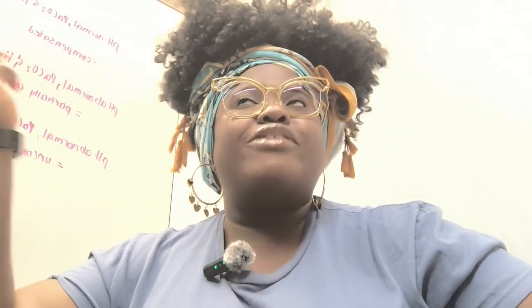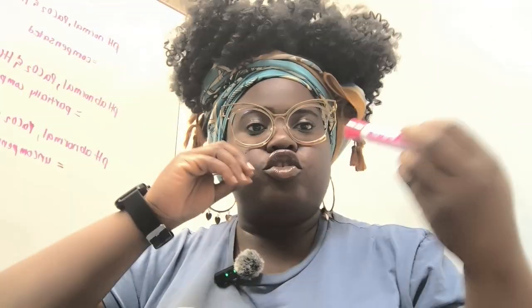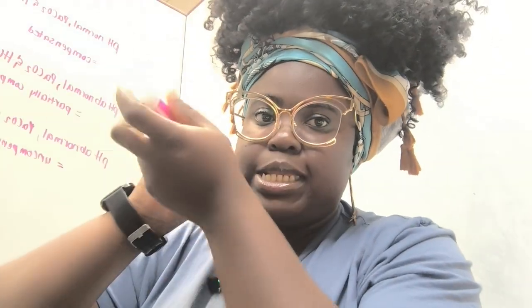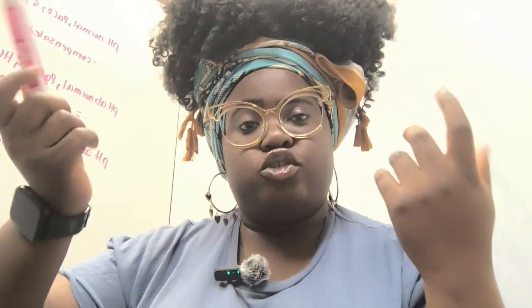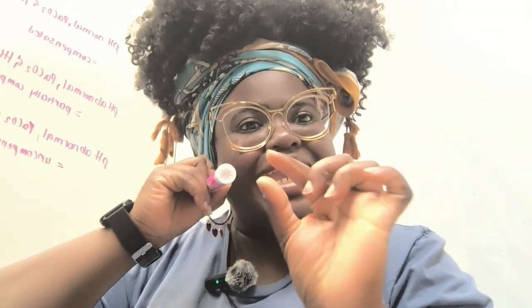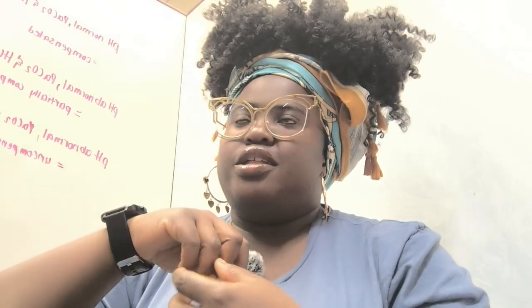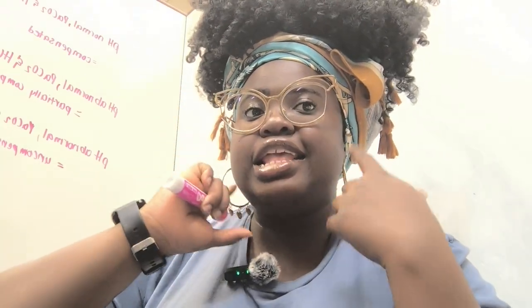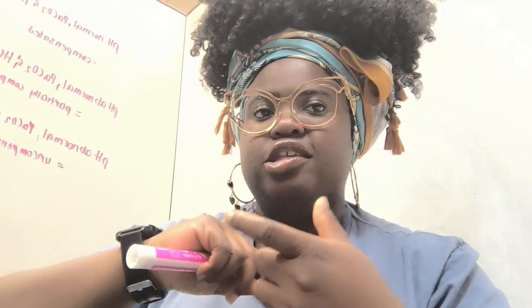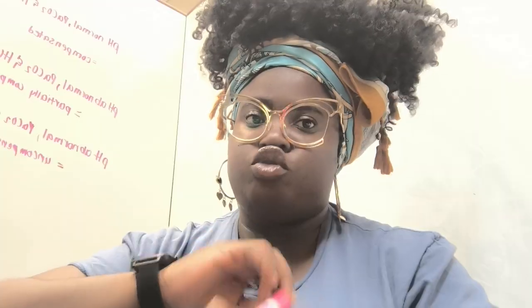Alarm two, low pressure. What does this mean? The ventilator is not building up enough pressure. What can cause it? Disconnected tubing. So the tubing to the patient is disconnected, which is the most common one. There's a leak in the circuits. There's a leak in the ETT cuff. The ETT is dislodged. Remember, ETT is endotracheal tube.